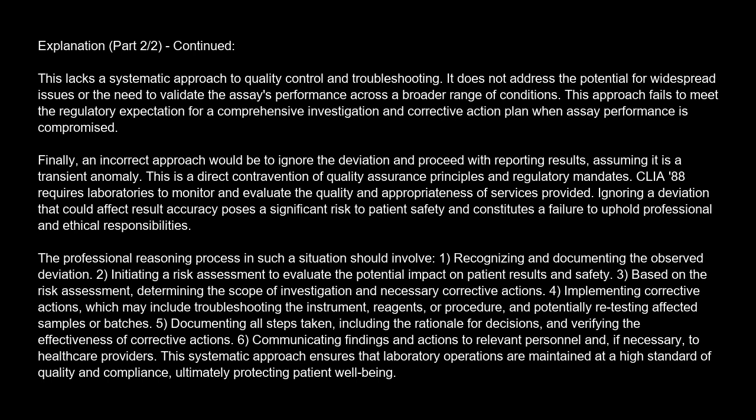4. Implementing corrective actions, which may include troubleshooting the instrument, reagents, or procedure, and potentially retesting affected samples or batches. 5. Documenting all steps taken, including the rationale for decisions, and verifying the effectiveness of corrective actions. 6. Communicating findings and actions to relevant personnel and, if necessary, to healthcare providers.